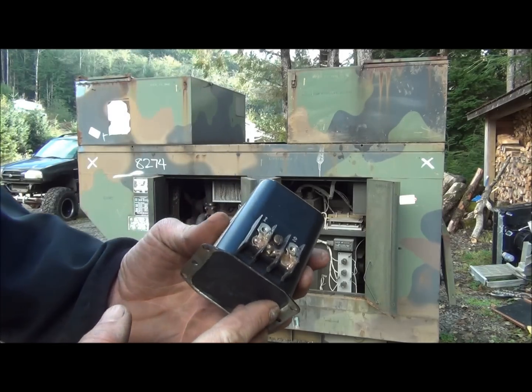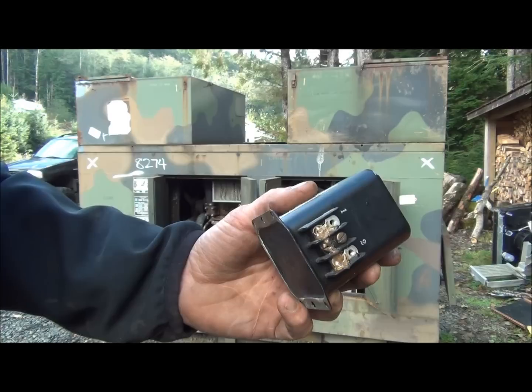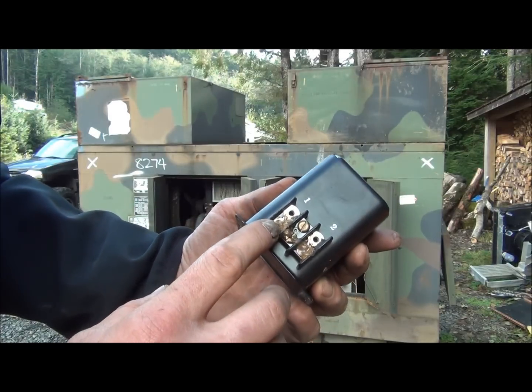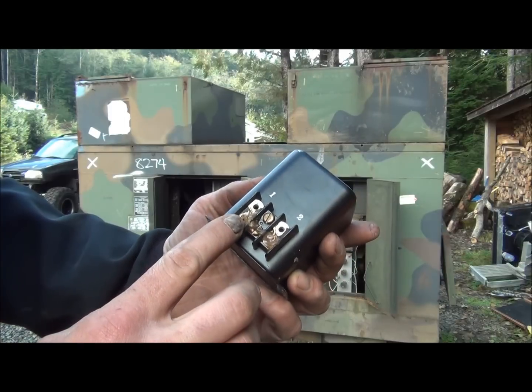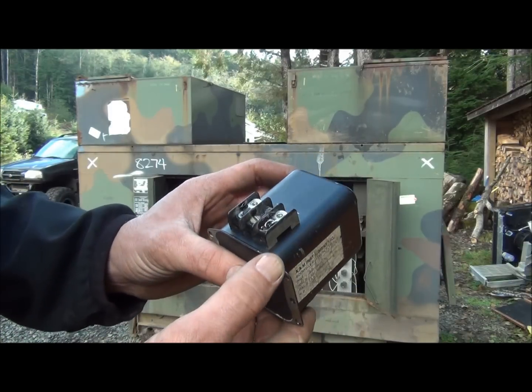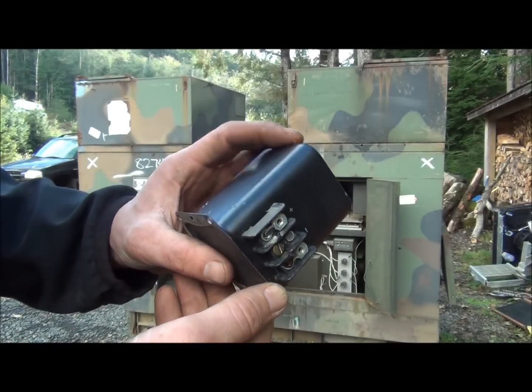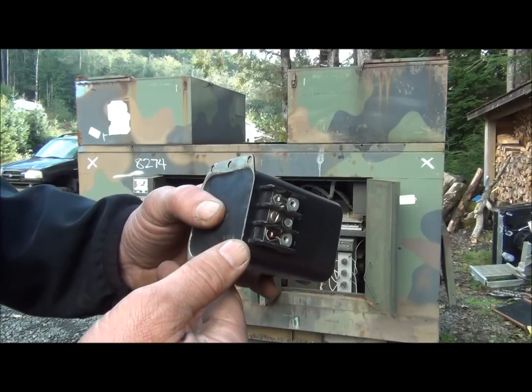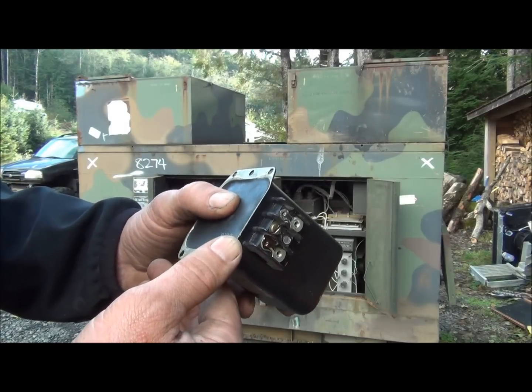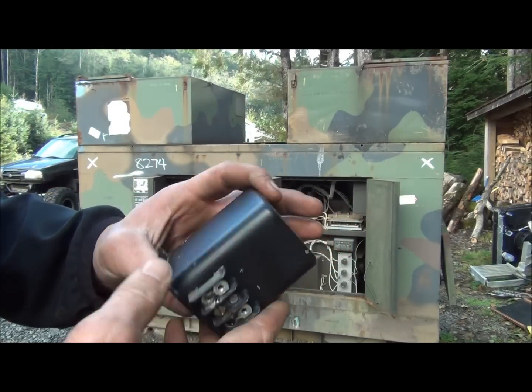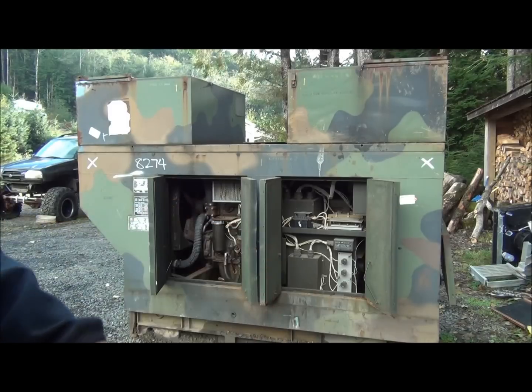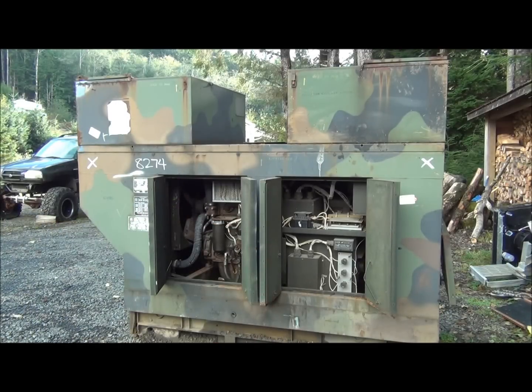This is the old frequency transducer right here. This is a non-adjustable type. You can see I have some kind of black tarry substance that's leaking out of it. So this is definitely our culprit. It's just maybe exposed to moisture, or just possibly reached its end of life. So we'll go ahead and throw it in the trash and continue on with our generator testing.